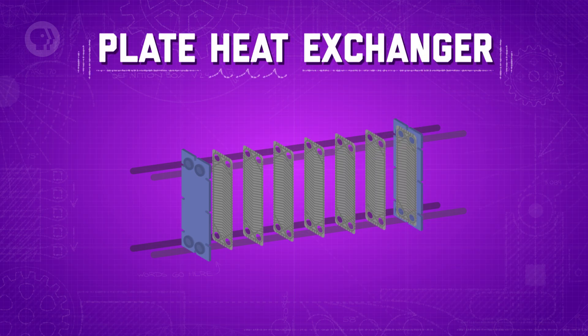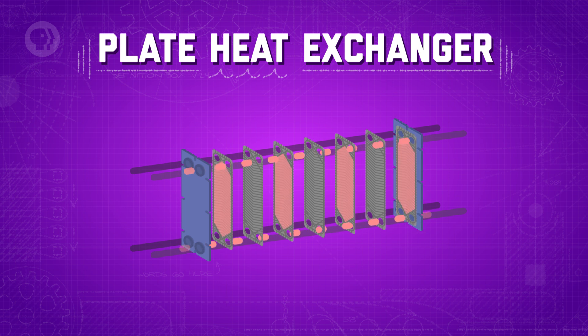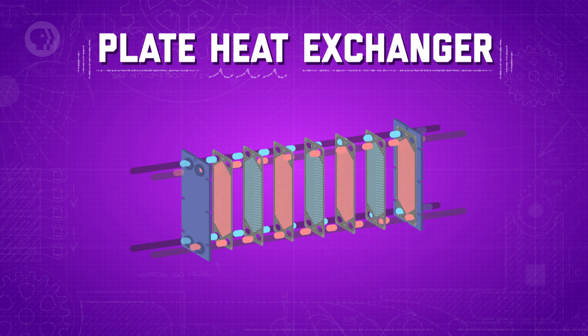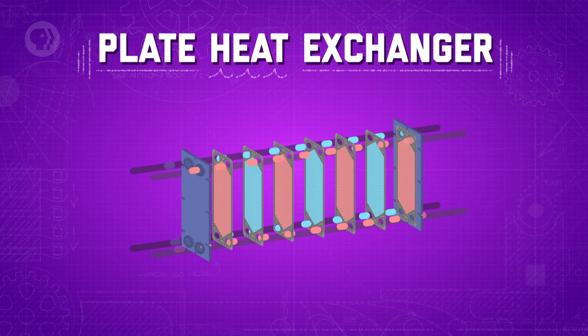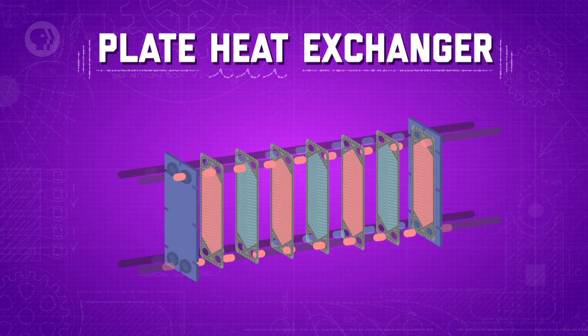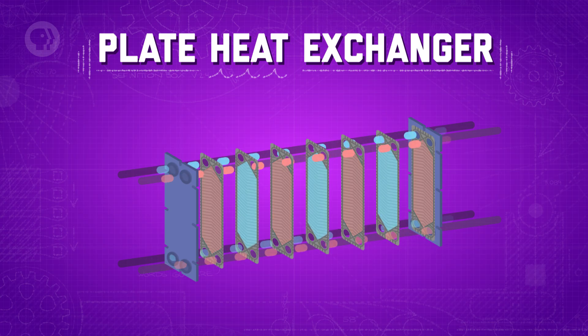Another heat exchanger worth looking at is the plate heat exchanger, which uses metal plates to transfer heat between fluids. The warmer fluid flows through one port and the colder fluid flows through another, typically in counterflow. Both fluids are restricted by seals so they can only flow in a certain path, kind of snaking their way through the exchanger. The fluid between each set of plates alternates, with the plates providing a large surface area for a high rate of heat transfer. Plate heat exchangers would be a little better than concentric tubes for something like an x-ray machine, since it produces a lot of heat you'd want to get rid of.